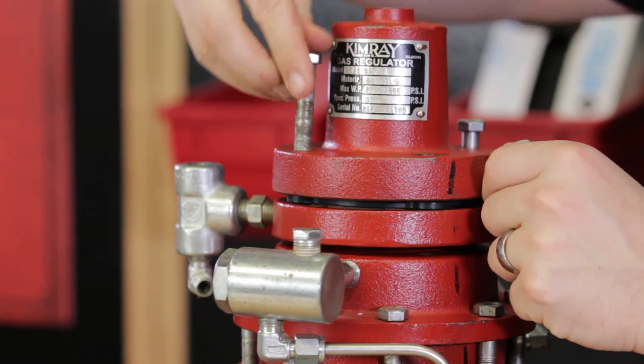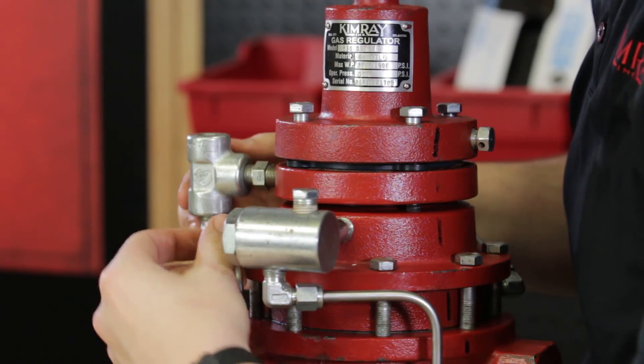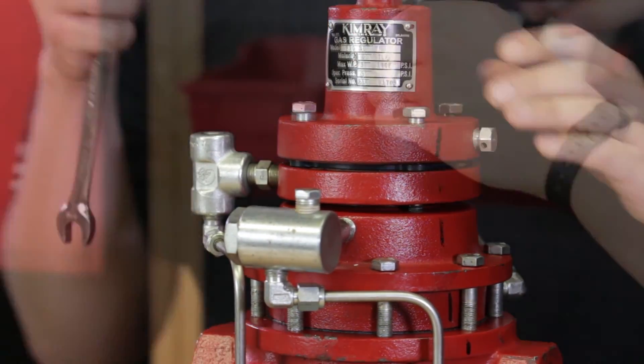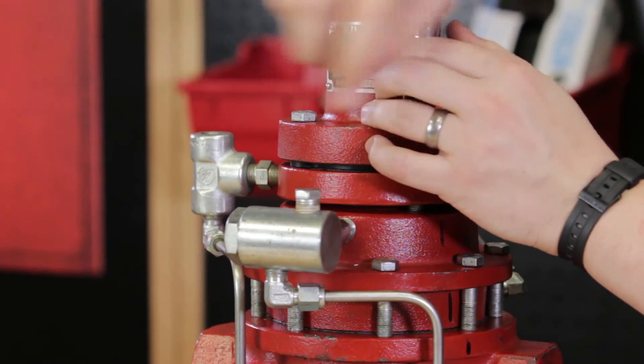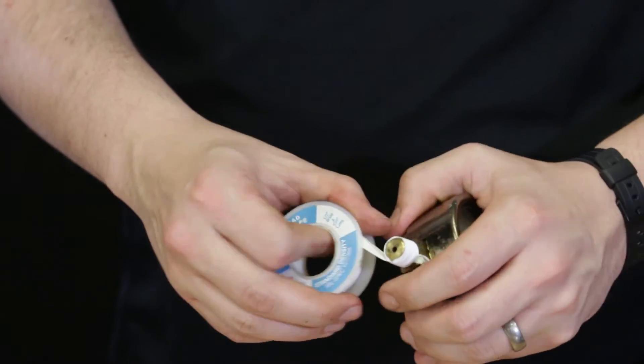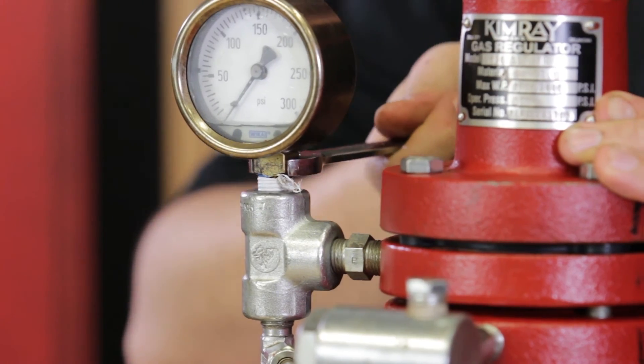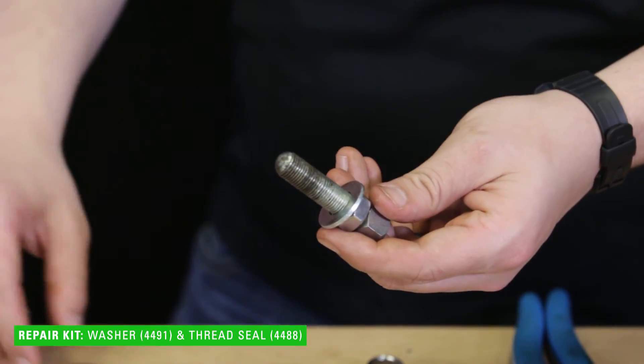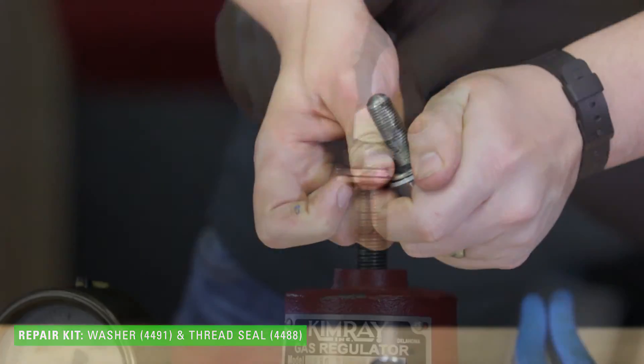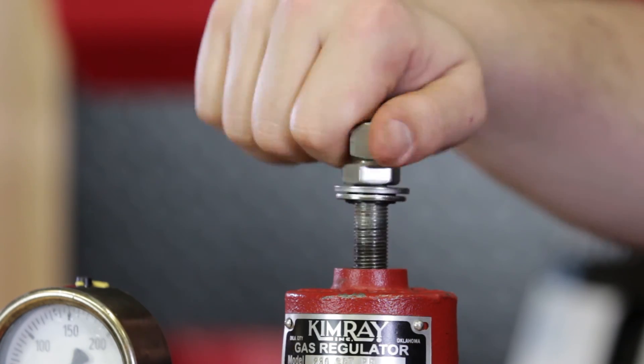Place the bonnet on the valve and start the bolts by hand. Install the rest of the tubing, then fully tighten the bonnet bolts. Reinstall the pressure gauge with thread tape. Attach the new washer and thread seal to the adjustment screw and thread it into the bonnet. If you have any questions about the Kimray tools used today, reach out to your local Kimray representative.